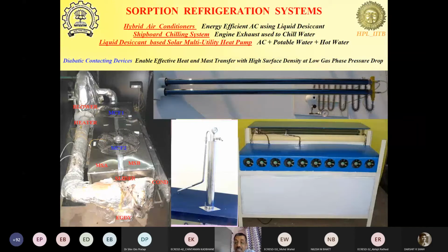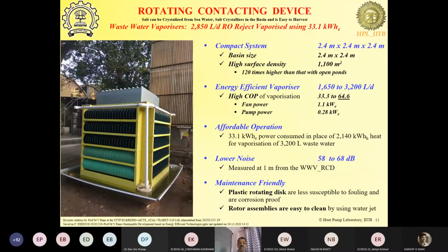And the dilute liquid desiccant is then regenerated using the condenser heat. So the condenser heat is used to regenerate the dilute liquid desiccant, and that reduces the condensing temperature. Conventional air-cooled condenser with 35-degree ambient condition, which is the standard test condition, the typical condensing temperature is 54.4 degrees centigrade. But in our case, we could drop it down to almost 48 degrees centigrade also. So not only increasing the evaporator temperature, but reducing the condensing temperature concurrently helps improve the COP significantly, and up to 30 to 50% or even 60% improvement in COP is possible. So we'll see some of those things as we go along.